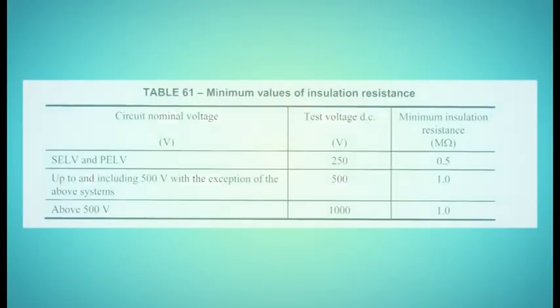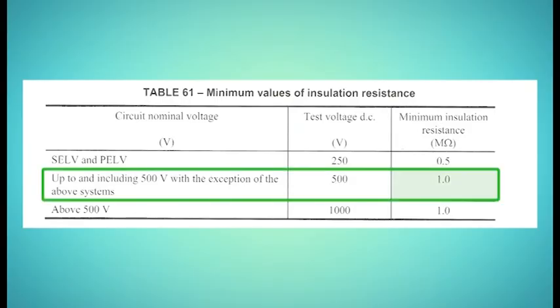The minimum acceptable insulation resistance for a circuit in the regs is 1 megohm. But an experienced inspector will need to consider very seriously whether readings approaching this level in an installation would be satisfactory. Consideration should be given to the age of the installation and previous test documentation, if any is available. If a low level of resistance was accepted, I would expect the inspector to reduce the time period for when the next EICR is due, because obviously the insulation is degrading.